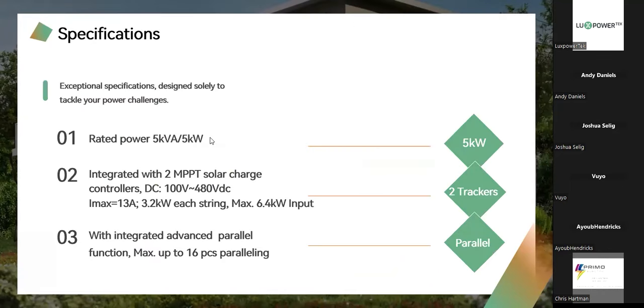Okay, so on the 5 kilowatt, the rated power is 5 kilowatt, 5 kVA. Here we're working on a power factor of 1, but obviously the machines are rated to go 0.8 leading and 0.8 lagging. So in the latter of the two, we should have a machine that can deliver up to 6.2 kVA.